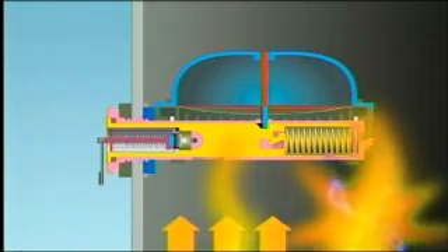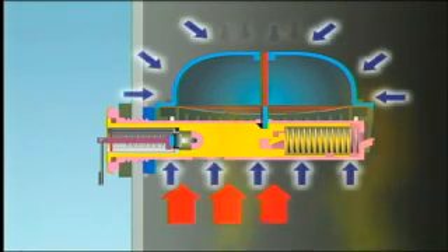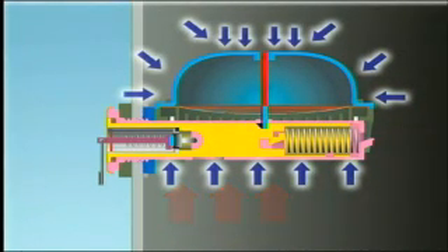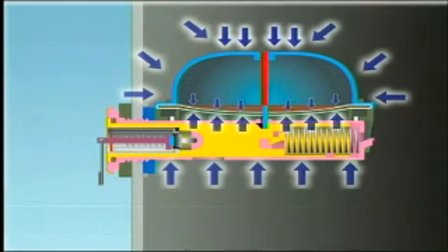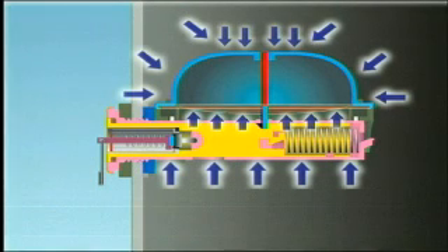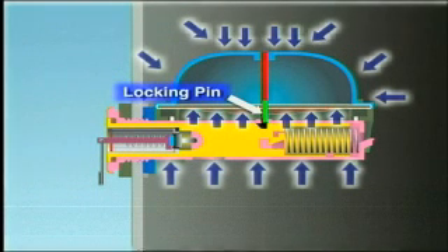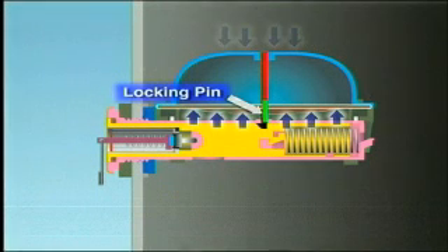When an internal fault occurs, the pressure increases suddenly. In this case, the metered hole in the IFD will not allow the pressure to equalize on each side of the diaphragm. Instead, the diaphragm moves up, releasing the locking pin, and causes the highly visible orange fault indicator flag to pop out of the side of the transformer.